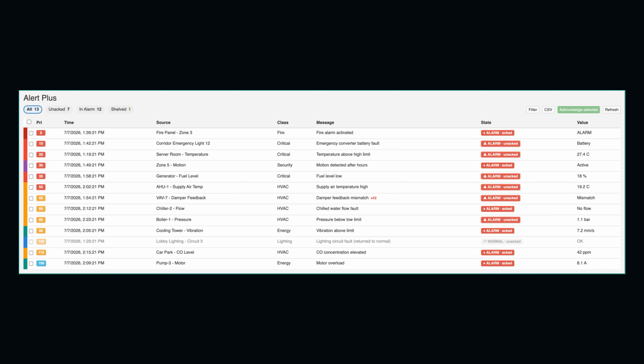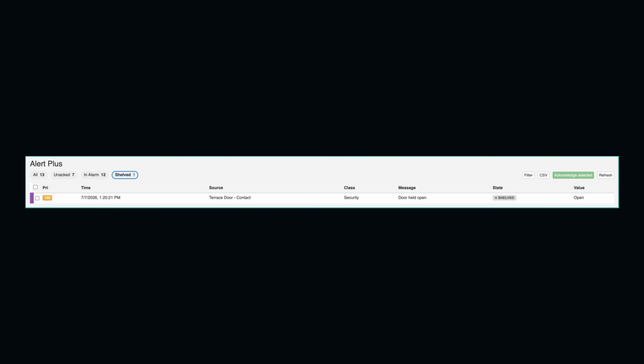Alert Plus does not treat an alarm as a simple on-off record. It manages every alarm as a live record whose state it follows from the moment it appears to the moment it closes. Both the condition an alarm is in, normal, off-normal, fault, or information, and whether the operator has seen it, acknowledged, or awaiting acknowledgement, are tracked separately. When the alarm's condition clears, the alarm returns to normal on its own. When needed, the operator can shelve an alarm temporarily, silence it for the duration of maintenance, or mark it out of service.